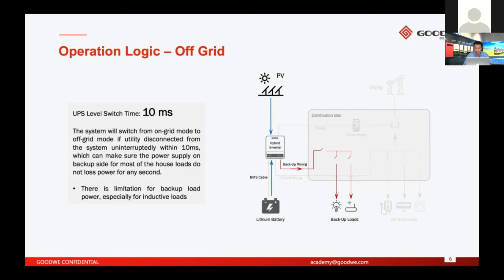A lot of suppliers, no matter whether from China or other countries, offer energy storage systems whose off-grid supply is EPS supply. This is a very big difference from GoodWe. GoodWe has a UPS-level switch time, which means there's no stop. But with EPS, if the grid fails, the loads will shut down for a few seconds, then start up again. This is a big difference.